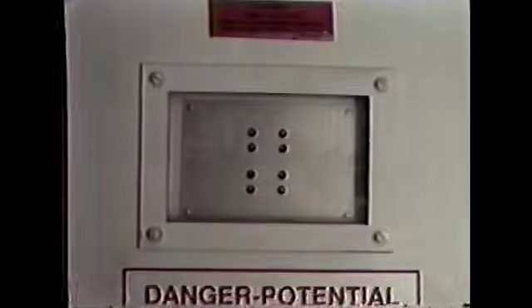A new feature on the Series 2 is this capacitor discharge indicator, or CDI panel, which is mounted on the door to the auxiliary control compartment. These indicators allow the operator to tell at a glance the status of the capacitor discharge inside the compartment. When the door to the auxiliary control compartment is opened, an interlock switch cuts out the high voltage supply to the compartment.